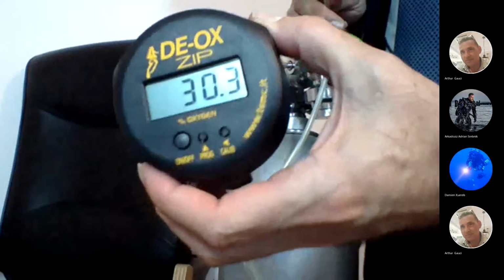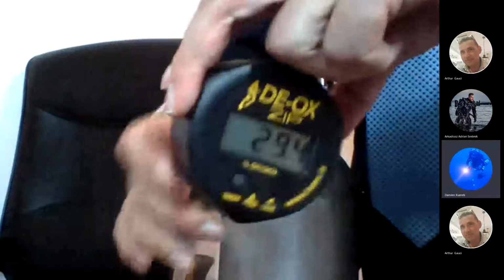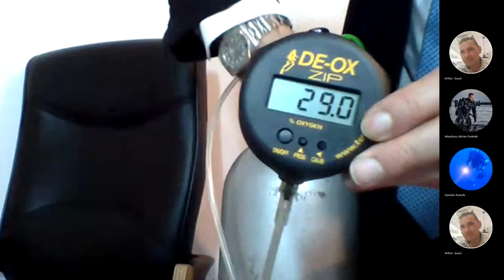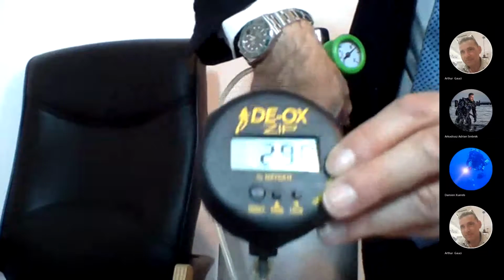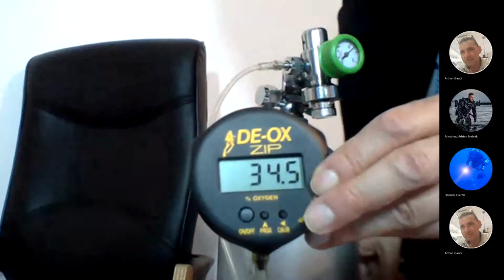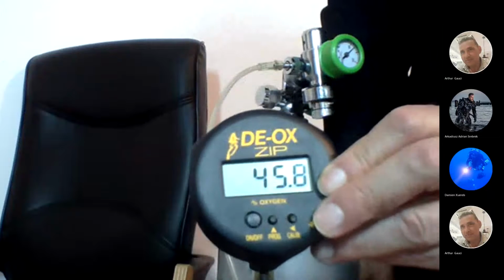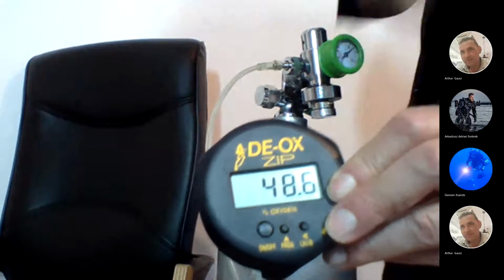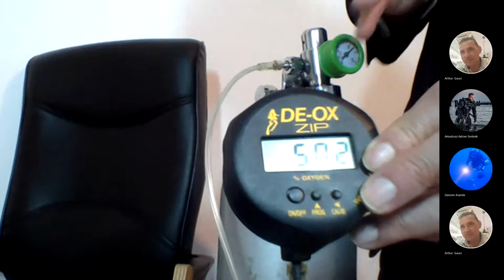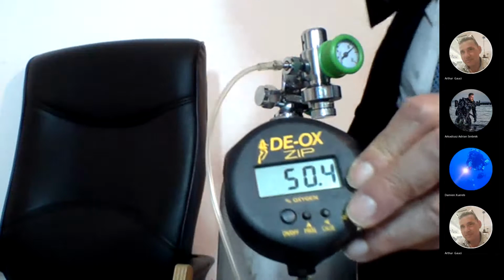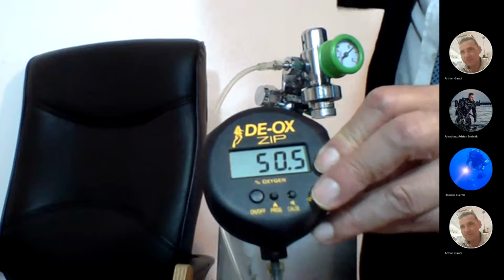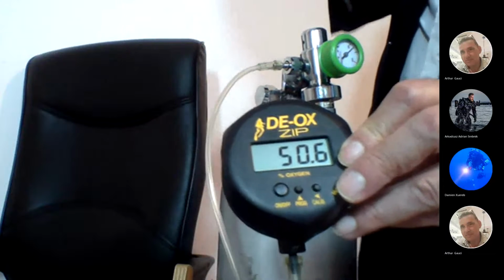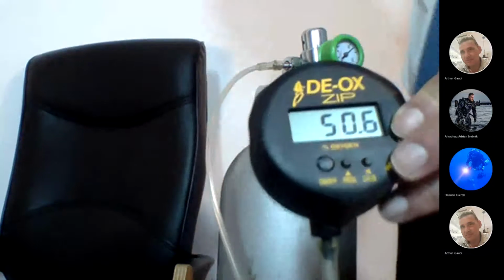And you see here the sensor didn't go back to 21%. No, doesn't matter, just connect. Okay, and now open. Flow again. Let's see what will happen. You remember the sensor was in air, was not showing 21%, was showing around 30%, but the sensor was already calibrated. Okay, so don't mind. If you did a good calibration, you don't need to go back to 21%.